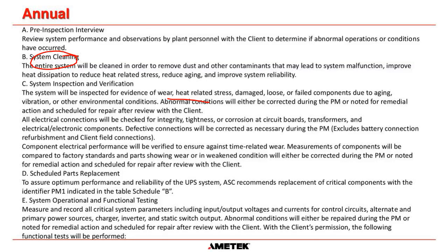What we also do now is every one of our field service guys, they carry a FLIR infrared camera, and we take pictures of all of the input and output terminations and anywhere else where power flows through the system to make sure there are no loose connections. And since we started doing this about 2 years ago, we have found many incidents of loose connections, and even where things have been miswired, and instead of being hot, they're completely cold when we expect them to be hot. So we do go through the whole system looking for connection issues. Obviously, if there's any parts in the annual PM, we would replace them, and I've got a slide for that later on. And then we do system operation and function testing.